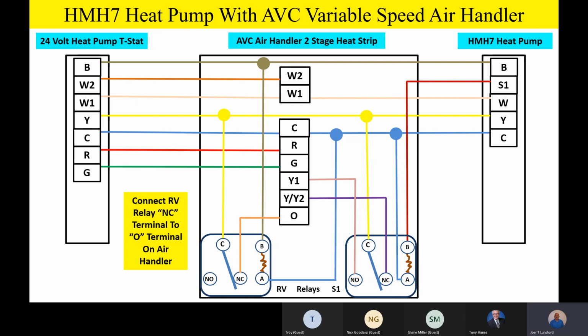So you're thinking right now, well, so what's the big deal? We're energizing the O terminal anytime we have a Y call on the thermostat. For compressor operation, we're energizing the O terminal as well in the cooling mode. That is correct. It's very, very important that we remember, on a heat pump application on a variable speed product, we have to tell the indoor unit it's in the cooling mode of operation, and we tell it that by energizing the O terminal.